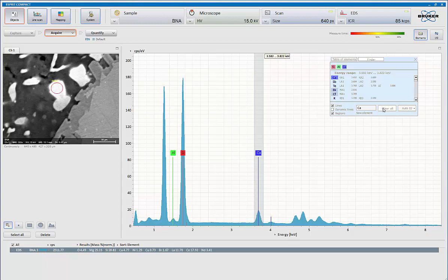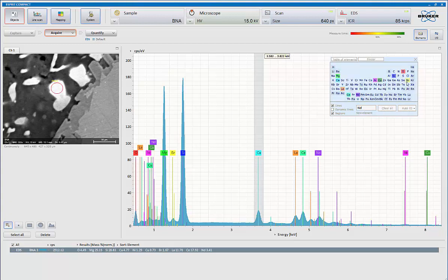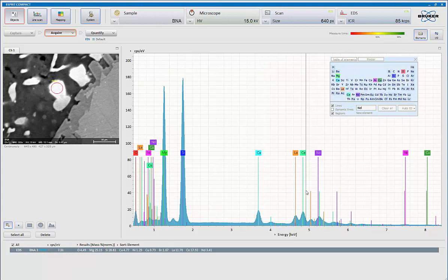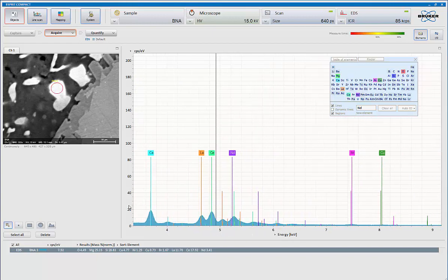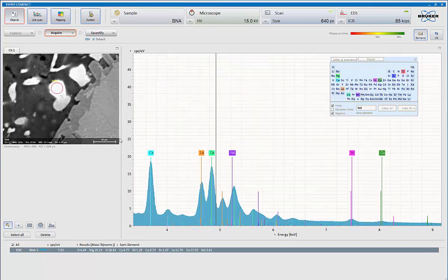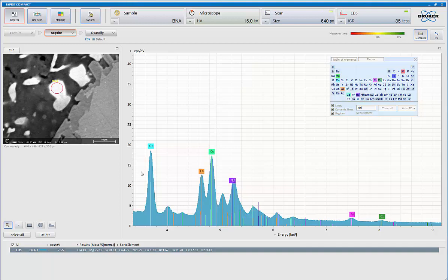So now I'm just going to quickly do a clear all to clear off all the possibilities. I'm going to let auto ID have a crack at this. So auto ID has come through here from the analysis set and this is the current ID that it's come up with. So it looks at this rare earth grouping and these are all the KLM markers it sees. I can then scale them dynamically and that looks pretty good. The problem is without breaking this overlap apart, I can't see all the components. Auto ID did it by basically utilizing quant, so it's doing a full quantitative analysis. So I can do that myself as well.